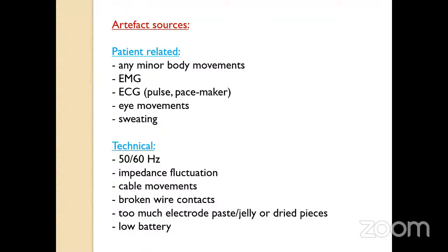One example: when we are measuring galvanic skin resistance, if the person sweats more, because of the variation in impedance, it's definitely going to give a wrong value. These are some examples where the human or patient itself adds some noise to the signal. Then apart from patient related noise, we have technical noise also introduced into the signal. For example, 50 or 60 hertz noise. Every machine is connected to the power supply, and the power supply has a constant frequency. In India it is 50, and abroad it is 60 hertz.